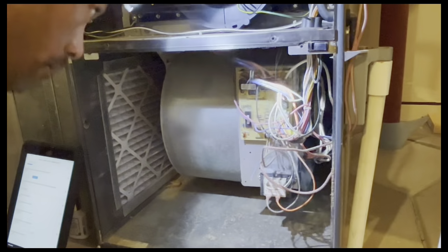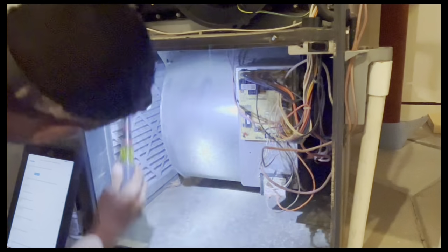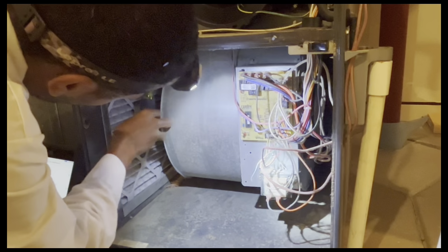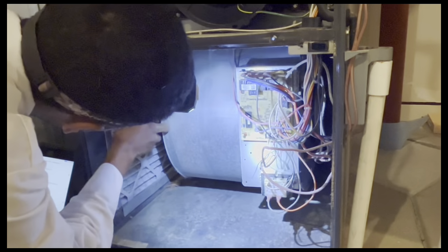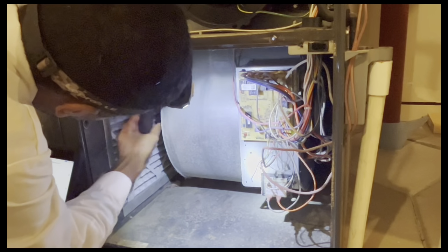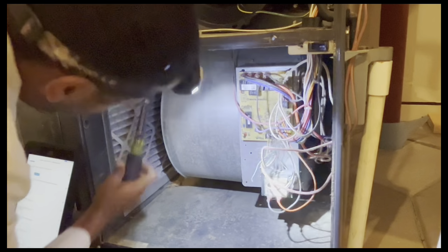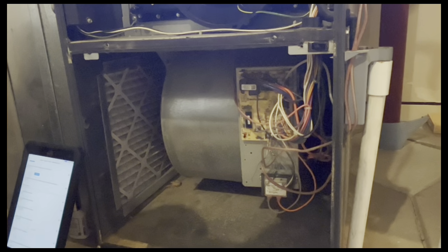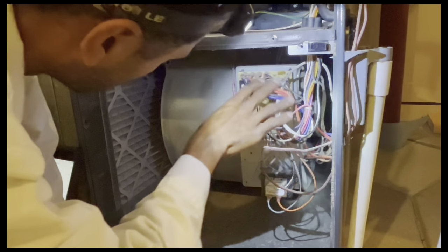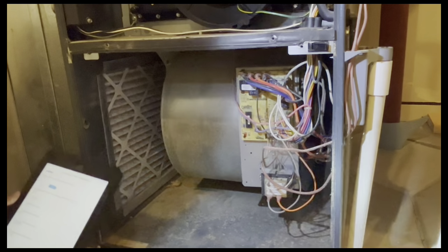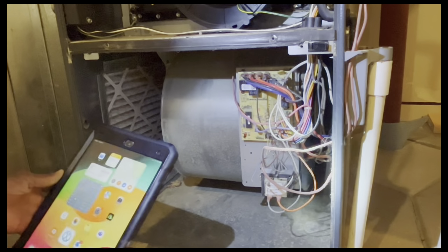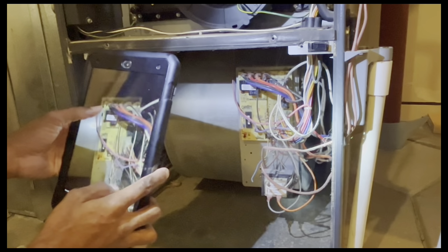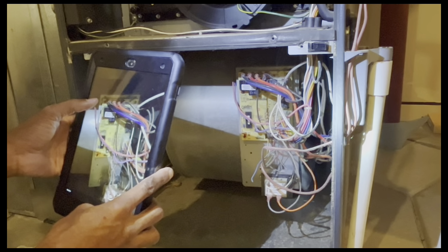So now I'm here looking at this blower housing and the circuit board down there, and I'm gonna go ahead and pull that out. This furnace, from what I remember, did have quite a bit of dirt and debris inside of it, and you'll be able to see it once I pull that blower wheel out, and you get some access to the actual secondary heat exchanger. This is a high efficiency furnace, so it's more of like a 95% efficiency furnace versus an 80%er. So this one has a secondary heat exchanger that condensates water and stuff like that. And the thing about it is that you want to make sure that you're keeping these furnaces filtered.